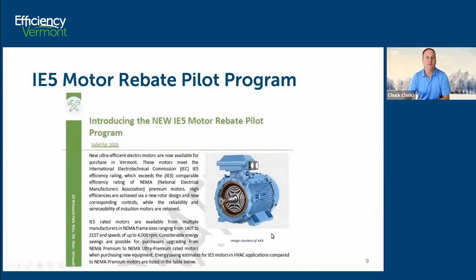There we go. Okay, so here's the IE5 motor rebate pilot program. Emphasis on pilot. We are running this pilot through the end of this year. Depending on the uptake, we may extend it into 2024, but we'll decide that later in the year. What are IE5 motors? IE5 motors are a two-step improvement over what we have had available here in the United States, at least since I joined Efficiency Vermont in 2007. In this almost 16 years I've been here, we have never been able to offer motor rebates, which is very ironic because 75% or more of the connected load in a manufacturing facility is motor load.